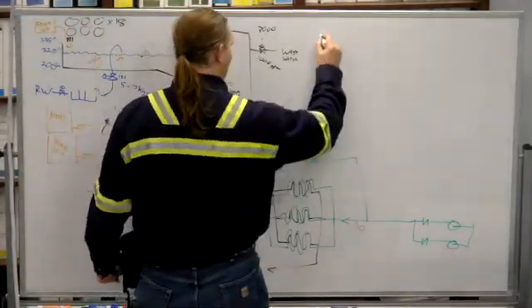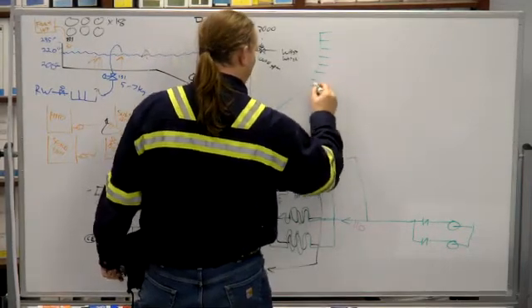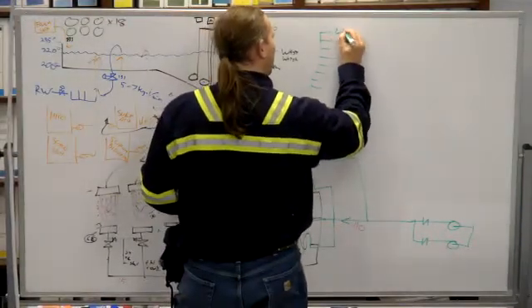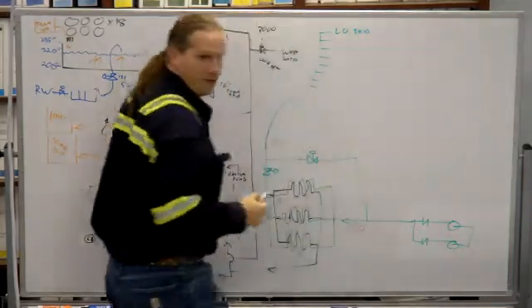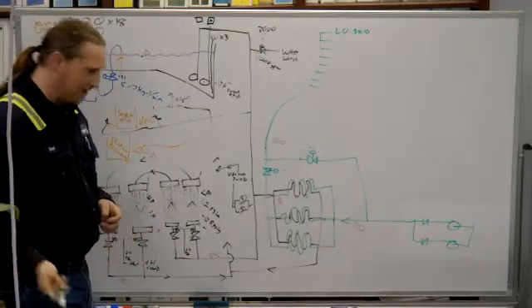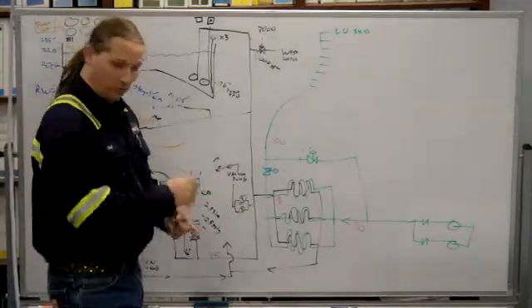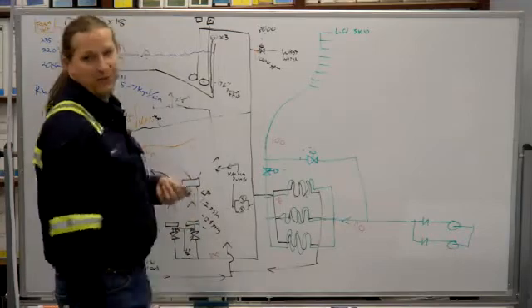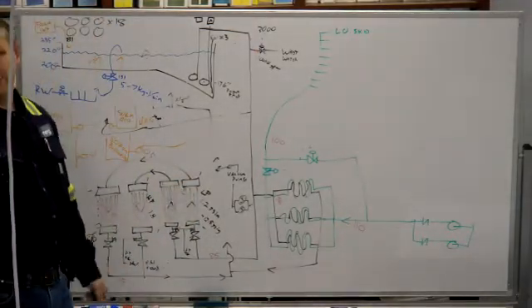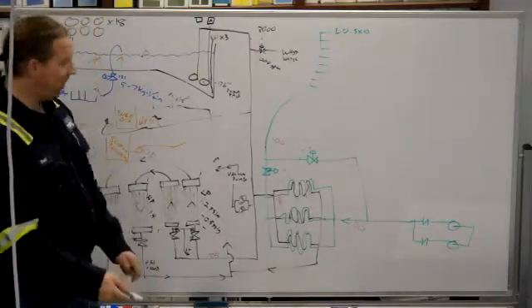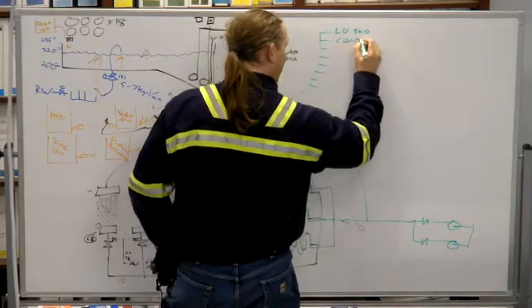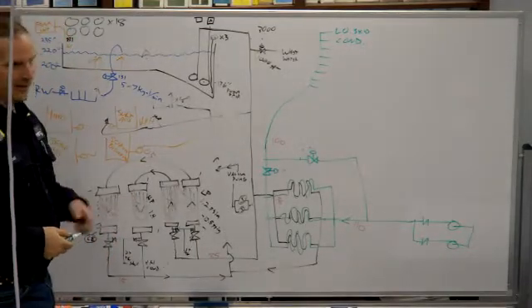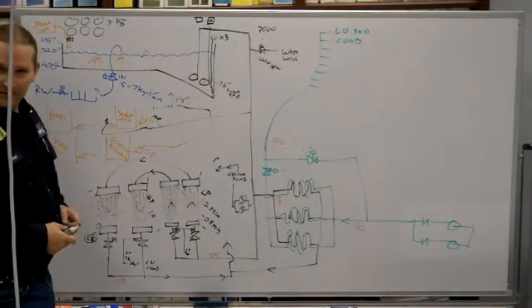So then this goes and cools a whole bunch of stuff. What do we cool with closed-cycle cooling water? Lube oil skids. With the exception of the ID fan, which is air cool. Lube oil skids - so the pulverizers, the main lube oil, the other four fans, the boiler feed pumps, rotary air heater. Condensate pumps - that's not a fan, not a lube oil skid. That is a motor that is directly water cooled. Stator cooling water.